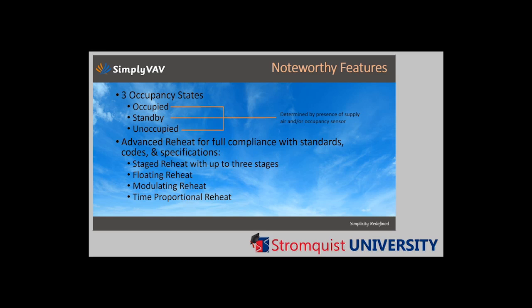On the reheat side, you can control up to 3 stages of electric reheat. On the modulating output side, we can give you either floating control, modulating control, or time proportional control of your hydronic reheat valve. So I think we got most of the applications covered on the reheat side.